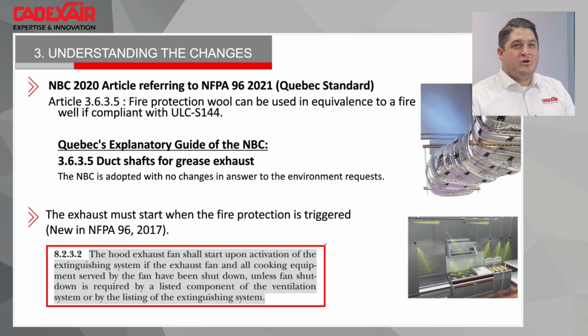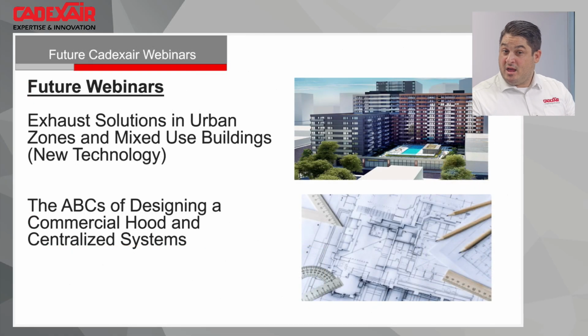But I will say, as per my experience, normally before, they would say the exhaust fan will stay in the same state it was in when the fire protection system was triggered. But we got a lot of calls about, no, the fan needs to be shut. But now this is what will be required. Something is sure, when you work with the Cadexair control panel, we can just go inside the control panel through the touch screen and set what they want locally. So when we're stuck at the last minute, it's really easy to fix, but it's something that you need to understand. Now when you buy a kitchen exhaust hood system, the fan will start when the fire protection system is triggered.